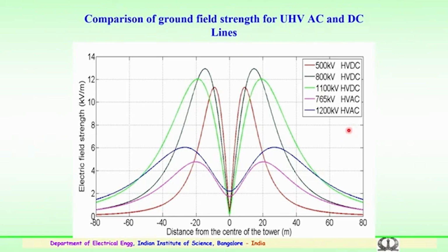So, comparing the 1100 kV HVDC and 1200 kV HVAC, or 800 kV HVDC and 765 kV HVAC, you can see the electric fields will definitely be higher in case of HVDC, slightly higher, and for HVAC with proper transposing the fields will be lesser.